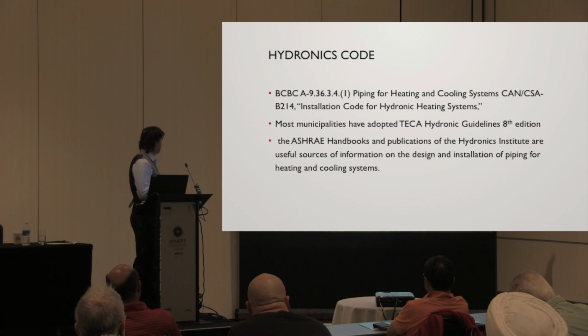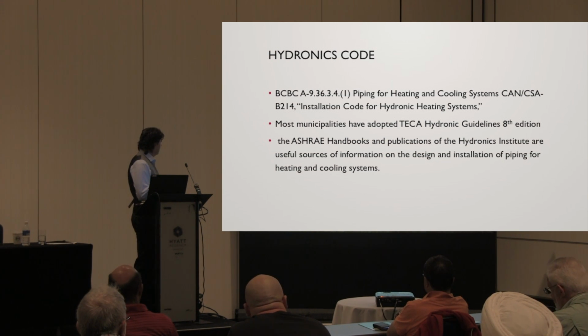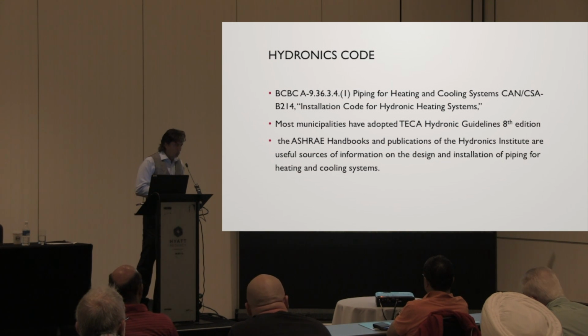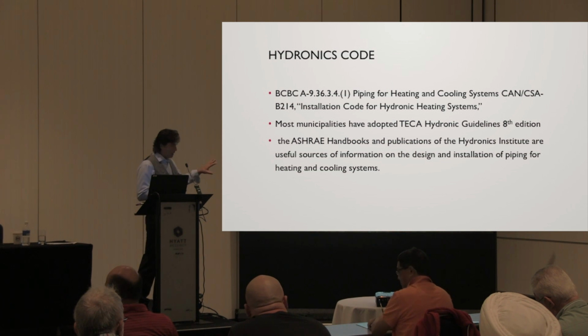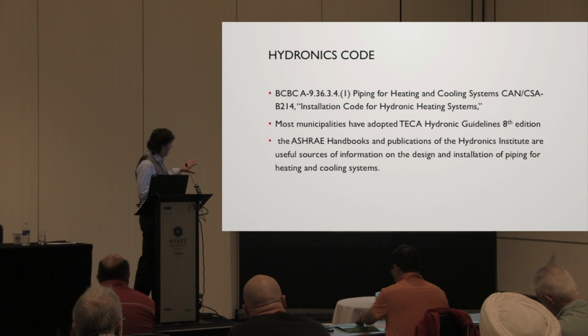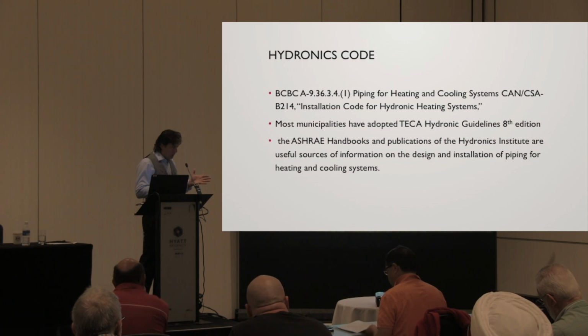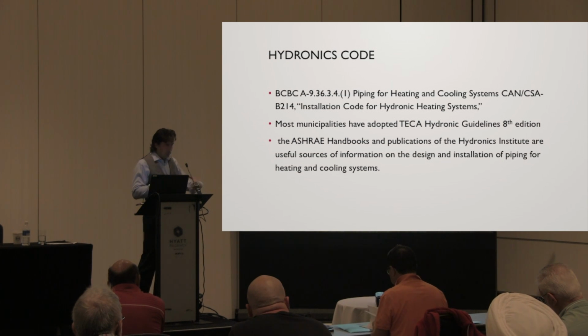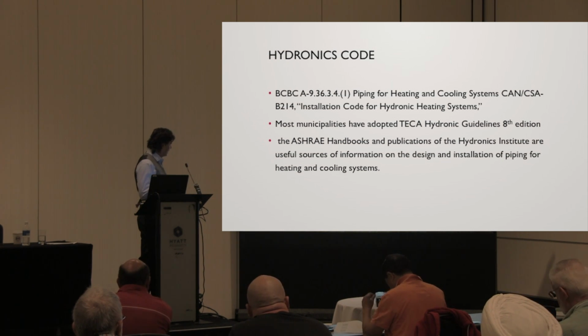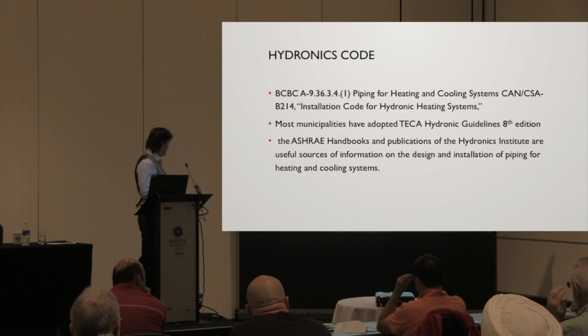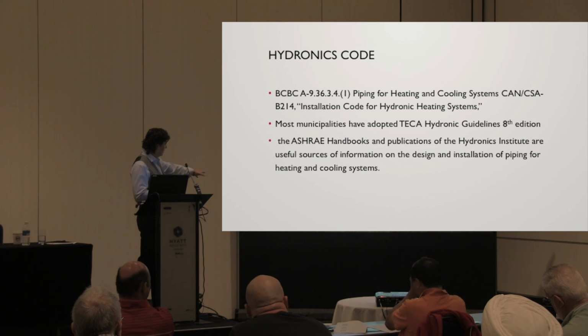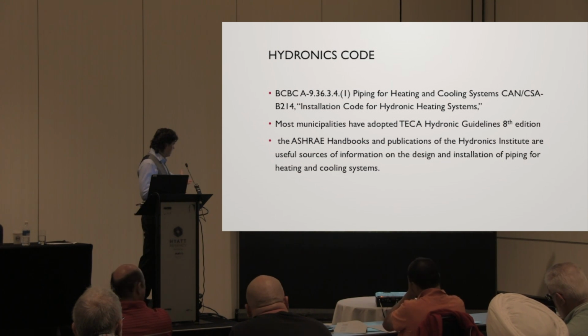Okay, start off with the code. BCBC, the energy code, 9.36.34, piping for heating and cooling systems. The building code would refer, when we talk about hydronics, to the CSA standard, which is B214, installation code for hydronic heating systems. Most municipalities have adopted our TECA guidelines, like I say. And when I say most, Vancouver does not do any inspecting of heating, but however, West Van, Surrey, Langley, etc., all use our hydronic guidelines. North Vancouver. Other good publications on it was, of course, ASHRAE and the Hydronics Institute, great sources of information when you want to talk about hydronics.